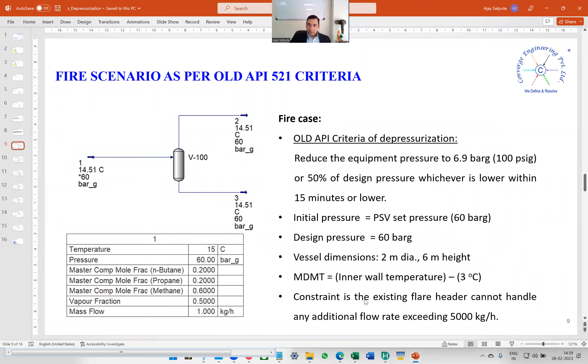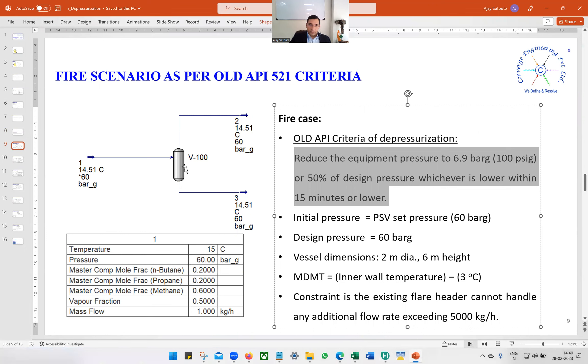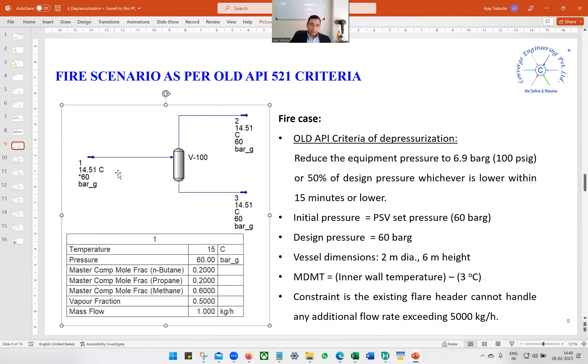Let us solve an example to make things clearer. We are going to study the fire scenario as per old API 521 criteria — depressurize to 6.9 bar gauge or 50% of design pressure, whichever is lower, within 15 minutes. The system we have is a two-phase separator with an inlet stream, stream number one.